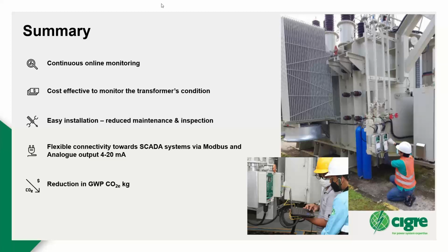No, that's all good. So from the graph, as the DP values decrease, the transformer obviously loses more age and has higher life loss. Is that reflected in the life loss calculations of the IEC standard? Yeah, it is, in the latest IEC standard. The Australian/New Zealand version is behind and doesn't really do it that well, so I'd say look at the IEC one.